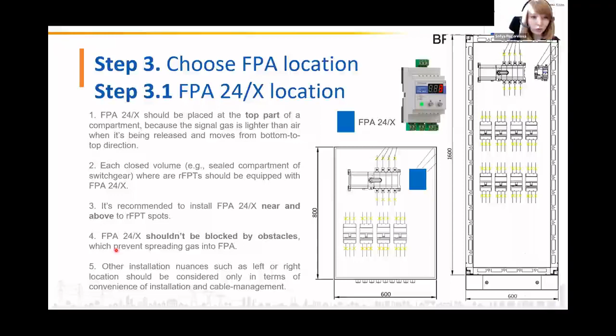Single gas sensor FPA-24X should be installed at the top part of a compartment, near and above to rFPT spots, and obstacles shouldn't block it. Next slide. Gas sensor FPA-24 with 4 coded sensors is installed in switchgear with several compartments to decrease the price per contact. It has the same requirements for installation as single gas sensor FPA-24X. Next slide. For the case with merged compartment without internal partitions, install gas sensor FPA-24 with 4 coded sensors in each section. One section shouldn't be bigger than 4 cubic meters.